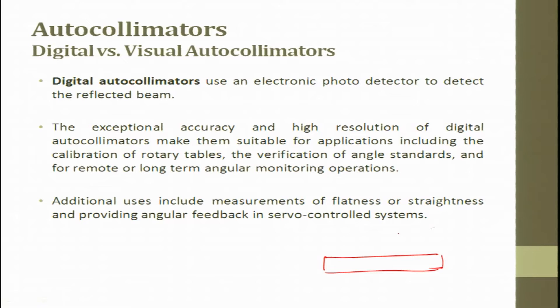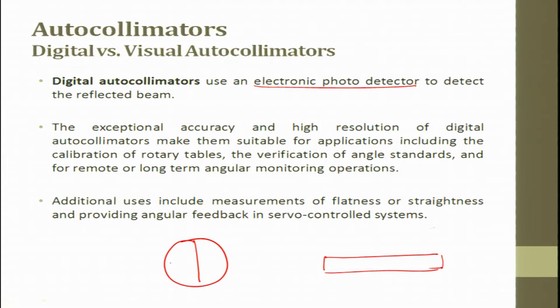The autocollimator can be analog — meaning visual-based — or it can also be digital. In a digital autocollimator, we use an electronic photodiode. The photodiode has four quadrants, or there are interference fringe patterns which can be counted. From those fringe patterns you can try to find out the displacement.